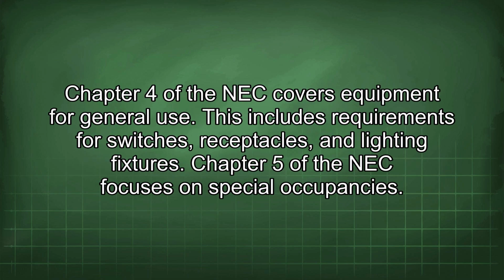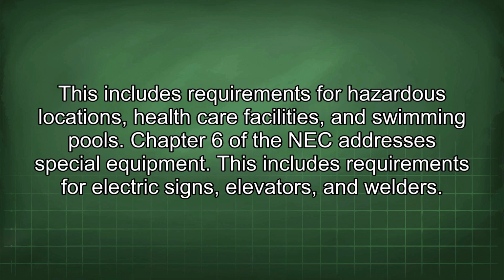Chapter 4 of the NEC covers equipment for general use. This includes requirements for switches, receptacles, and lighting fixtures. Chapter 5 of the NEC focuses on special occupancies. This includes requirements for hazardous locations, healthcare facilities, and swimming pools. Chapter 6 of the NEC addresses special equipment. This includes requirements for electric signs, elevators, and welders.